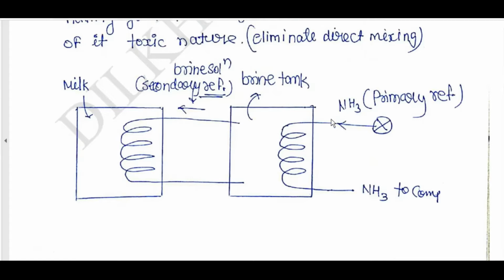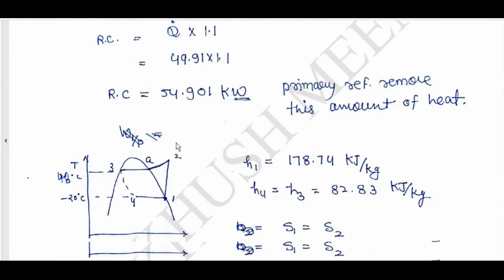NH3 is the primary refrigerant, which will be connected to the compressor, and NH3 will be running through the refrigeration equipment. But the brine tank is the one which rejects heat to NH3 and flows through the milk. From that, milk is cooled.